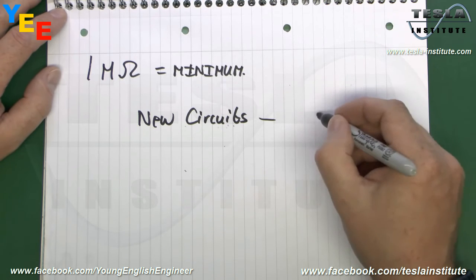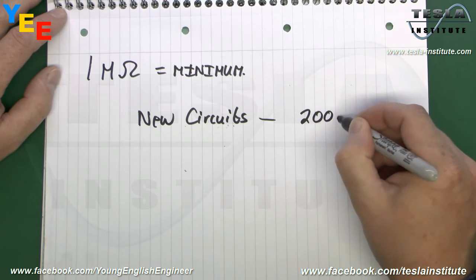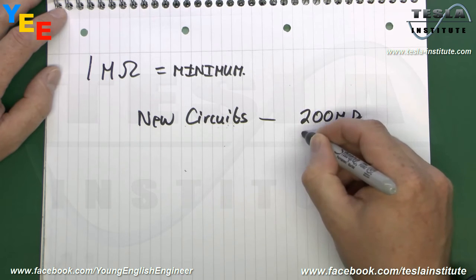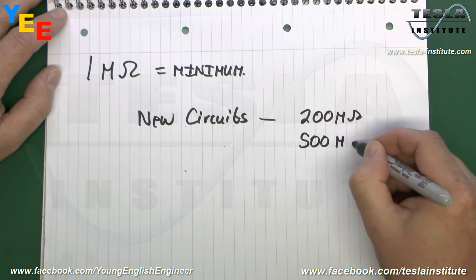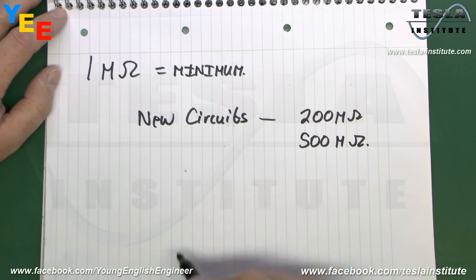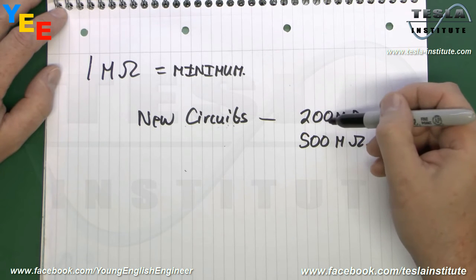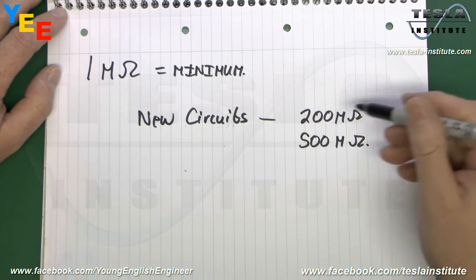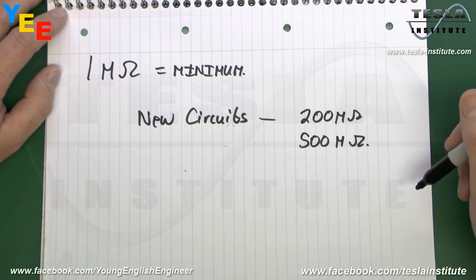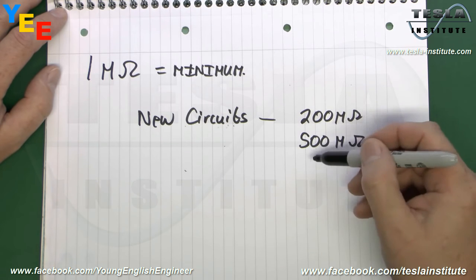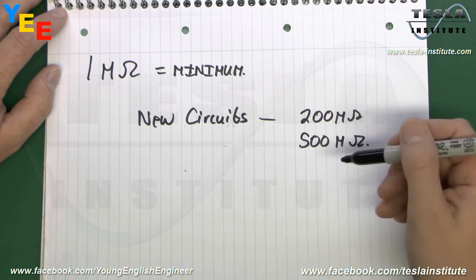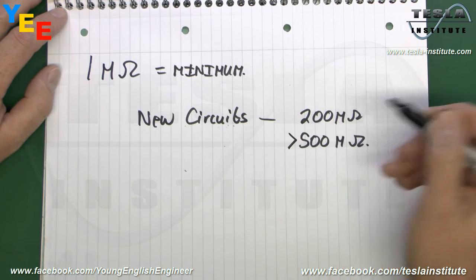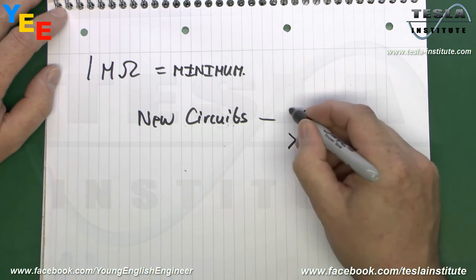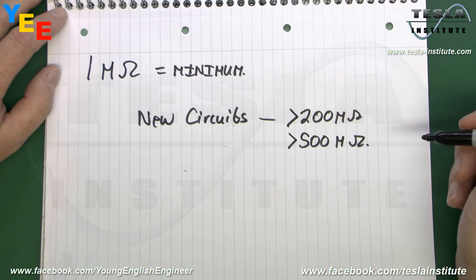Now, most test equipment either goes up to around 200 as a maximum reading, or in some cases 500. And for a new circuit that's just been installed, you should be seeing basically the maximum reading that the device can display, so either 200 or 500. Quite often it's just displayed as greater than 500 or greater than 200. And again, that's pretty much what you would expect to find.